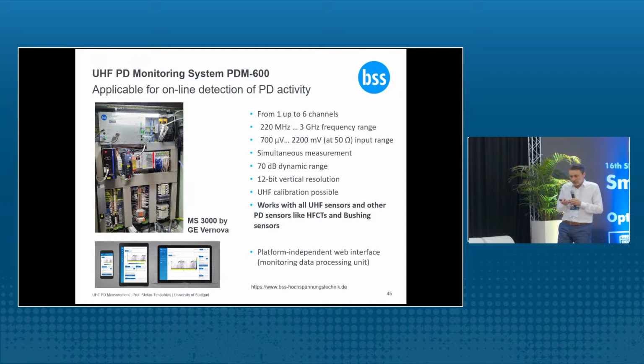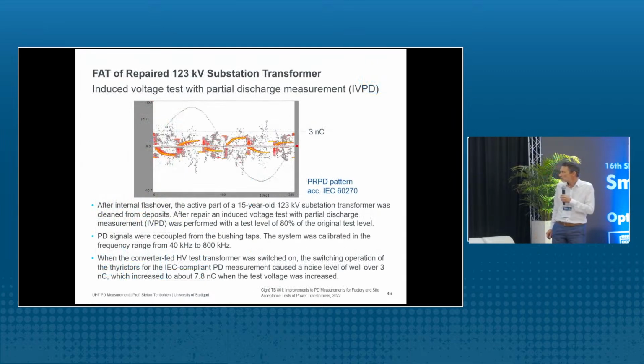But you can use this UHF also for monitoring purposes. What you can see here is a full monitoring system of a transformer, and this equipment here is the UHF PD monitoring system. One case of such a UHF PD monitoring I present here. This was a 123 kV transformer, and this 123 kV transformer had an internal flashover.